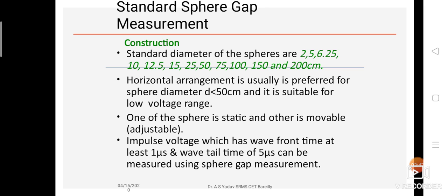From the standard tables, we determine the spark voltage with respect to the spacing between the spheres. Regarding the standards of the gap measurement and construction, the standard diameters of the spheres are 2 centimeter, 5 centimeter, 6.25, 10, 12.5 up to 200 centimeters. The horizontal arrangement is usually preferred when the sphere diameter is less than 50 centimeters, and it is suitable for the low voltage range. One of the spheres is static and the other is movable or adjustable. Impulse voltage which has a wavefront time of at least 1 microsecond and a wave tail time of 5 microseconds can be measured using sphere gap measurement.